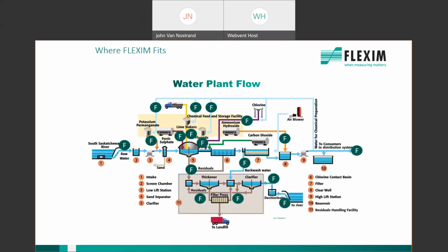So some of the applications: first I want to address the freshwater side, then I'll talk a little bit about the wastewater. From the production wells to the finishing section and all points in between, to include chemical injection of orthophosphates, for example, and sodium hypochlorite, FLEXIM offers the best chance for water balance as well. So any of these applications where you see an F in this diagram of a water plant is a great spot for a FLEXIM flow meter.